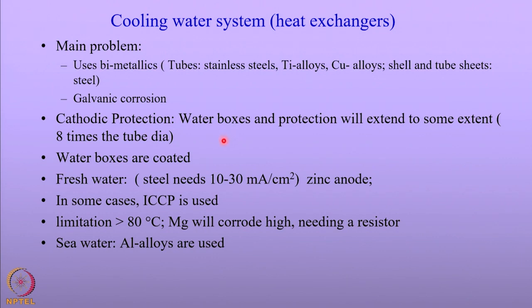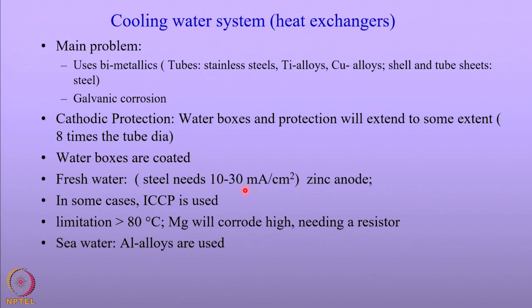The cathodic protection is generally done in the water boxes, and the protection will extend into the tubes to about 8 times the tube diameter. So galvanic corrosion in that location is significantly reduced. The water boxes are generally coated, and for fresh water, the current required lies in the range of 10 to 30 milliampere per centimeter square, and zinc anodes are generally used.